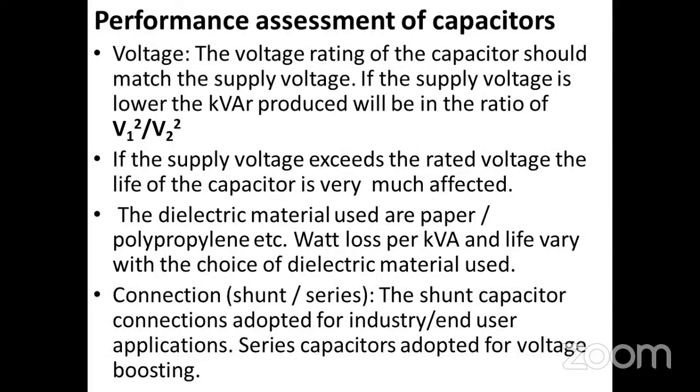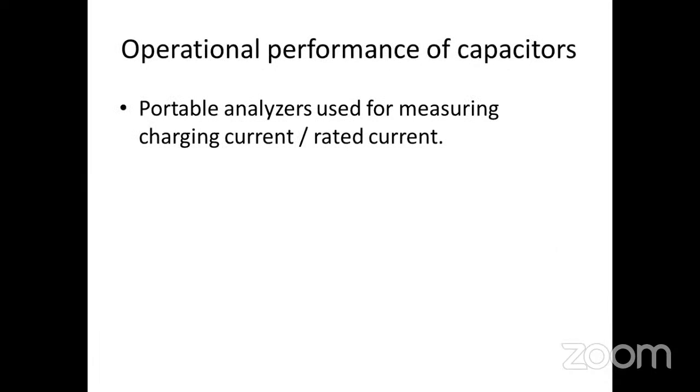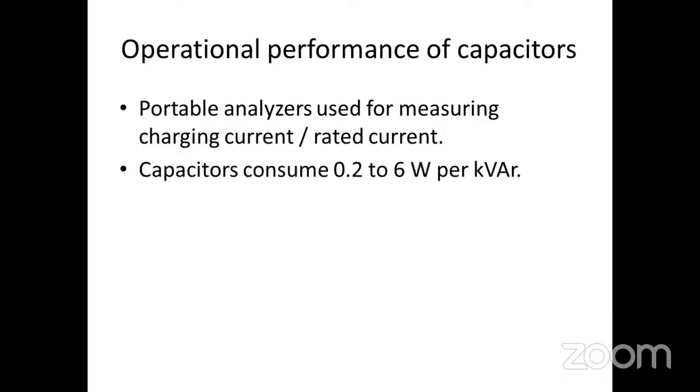Connection: shunt capacitor connections are adopted for industry or end user applications. Series capacitors are adapted for voltage boosting only. Portable analyzers are used for measuring charging current. Capacitors consume 0.2 to 6 watts per kVAR.